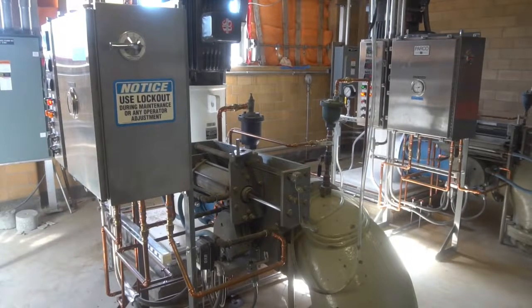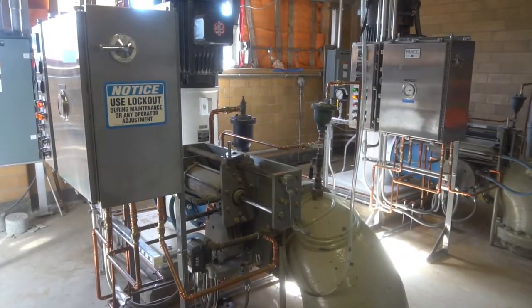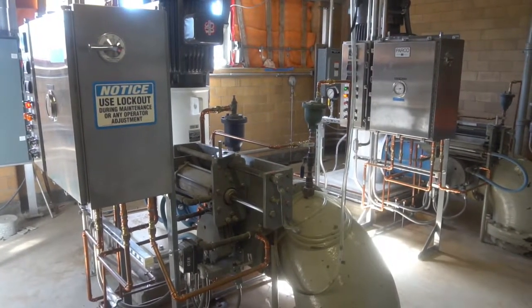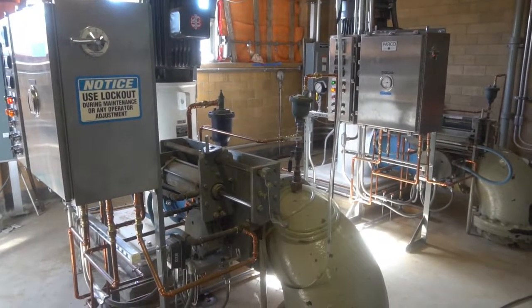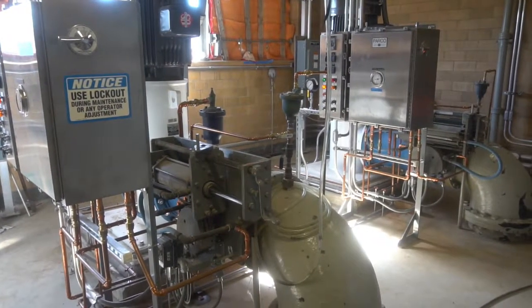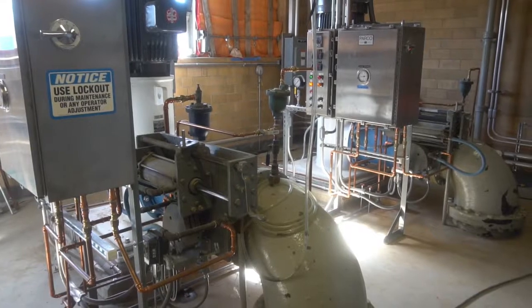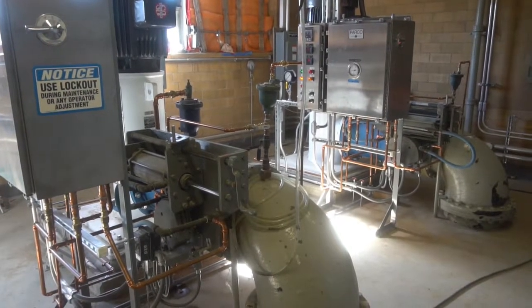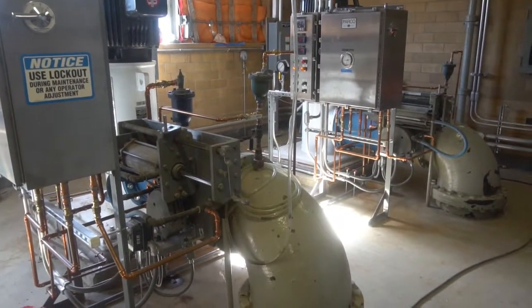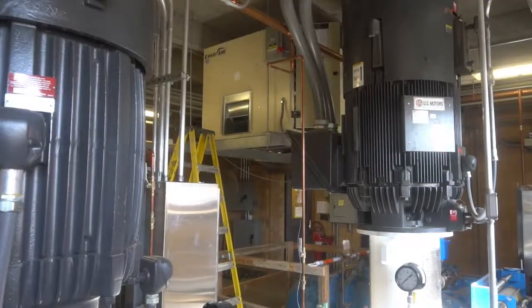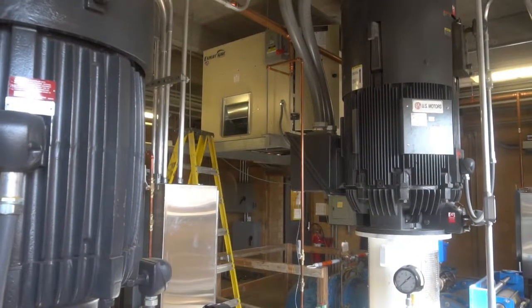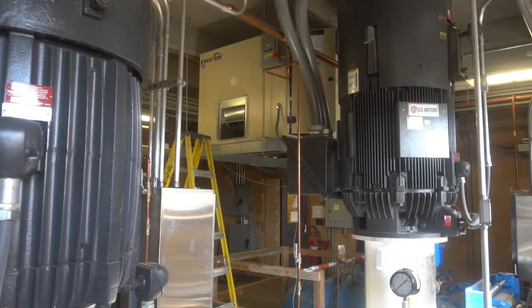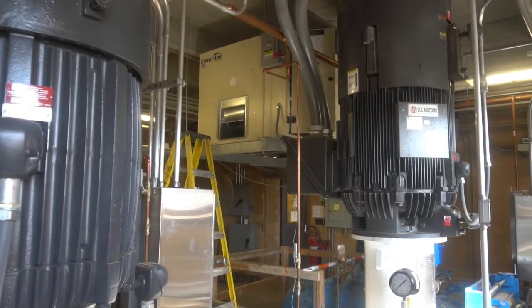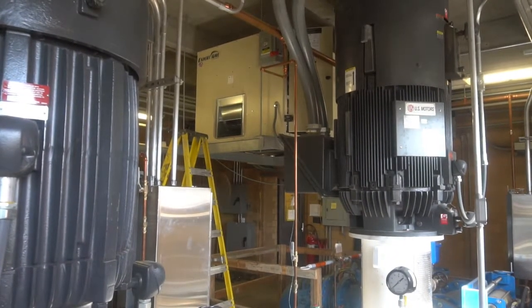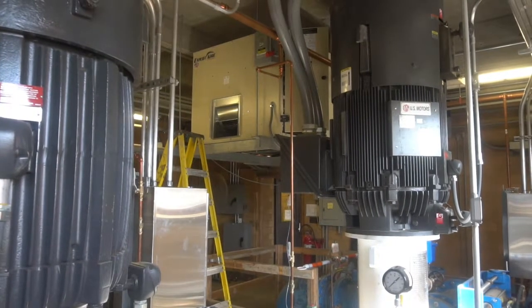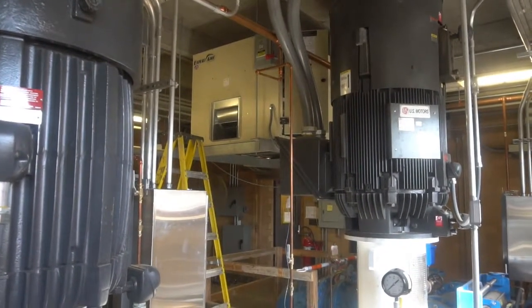Now we move into the intermediate pump room. They are utilized to draw water from the filtered water reservoir and fill the 2 water storage tanks to assist in both supplying the system and in backwashing filters. Note that one intermediate pump is larger. This 9 million gallon a day unit can pump directly into the distribution system, adding redundancy and resilience in the case of a failure with the other pump system.